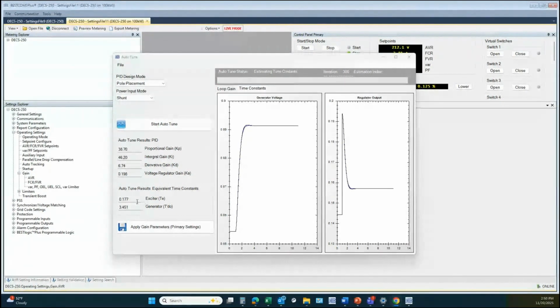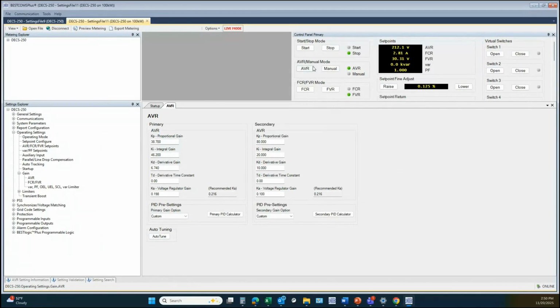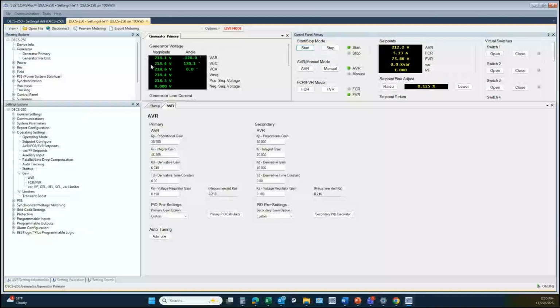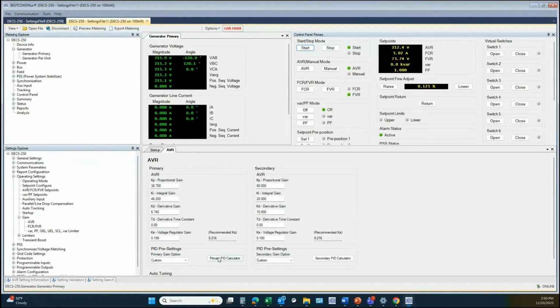As you can see, it provided some time constants for this machine that this DECS is controlling, and it provides some recommended gain values. So I can then apply those gains and then close out this window. If I then start the DECS, we will see that it will begin regulating. If we pull up the metering, you can see I'm regulating voltage. Probably being improved upon. I often recommend starting with a Ka value of something very low, such as 0.03. And then if you find that you need a more aggressive response, then go ahead and start bumping that up.